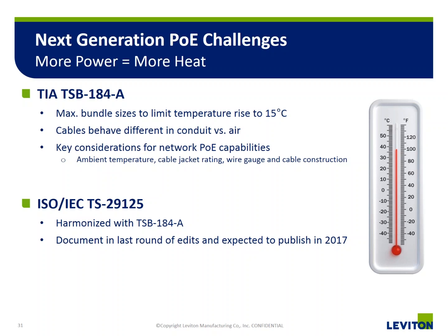Through the course of this investigation, we found that cables behave differently in conduit versus air. Several things need to be considered when you're designing network PoE capabilities. What is the anticipated ambient temperature? What's the cable jacket rating? Is it actually 60 degrees? Is it 75 degrees? Is it something different? What's your wire gauge and cable construction? The larger the wire, 23 gauge is going to perform better than 24 gauge because it's a larger size. What's your cable construction? It's been discovered that shielded cabling, with foil around the outer jacket or foil around the pairs, can perform better than unshielded cabling when you're talking about heat dissipation.